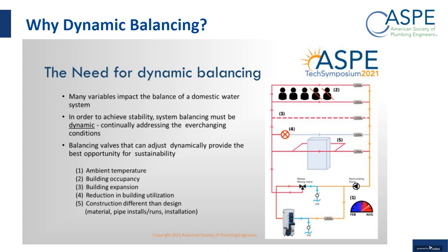And then there can also be, again, building reduction. Especially now with a lot of people working remotely, you can have these commercial buildings and they may be shutting off certain floors because there's no occupancy. But with the manual balancing valve, shutting off those floors changes the balancing of the whole system. With a thermostatic balancing valve, you don't have to worry about that.